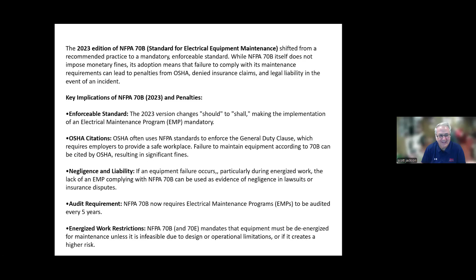With it being shifted from a recommendation to now an enforceable offense, OSHA will come in and penalize you after the first offense if you do not do your energized or de-energized maintenance, if you don't have an active arc flash study, or if there's some sort of incident on site. The first violation, a serious offense, is up to $16,000, and that's per violation.